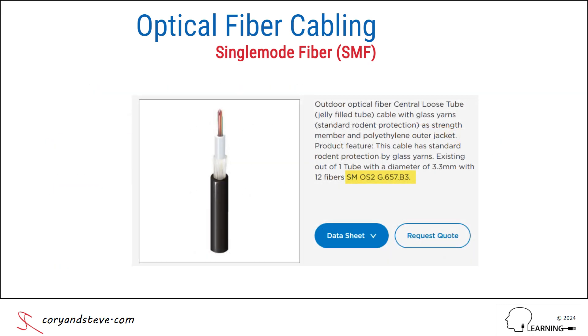Here's an example of an outdoor OS2-rated single-mode cable. Note the vendor's specification of the type of fiber strands it contains — in this case, it's G.657.B3 bend-insensitive fibers, with a minimum 5 mm bend radius.